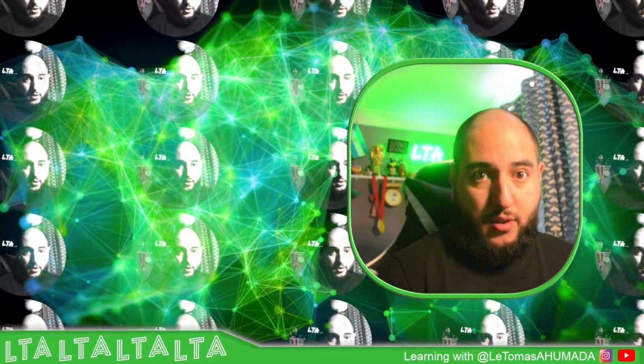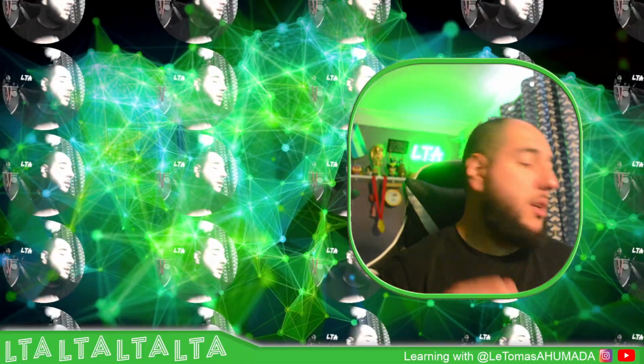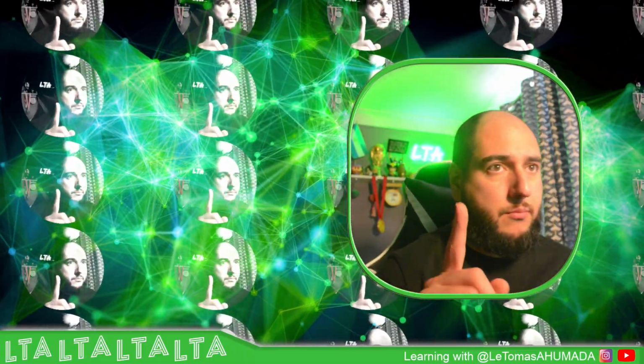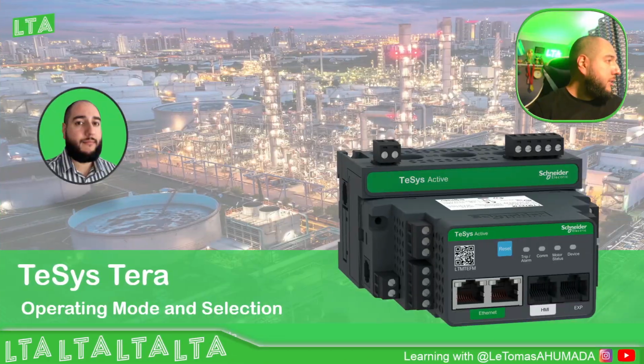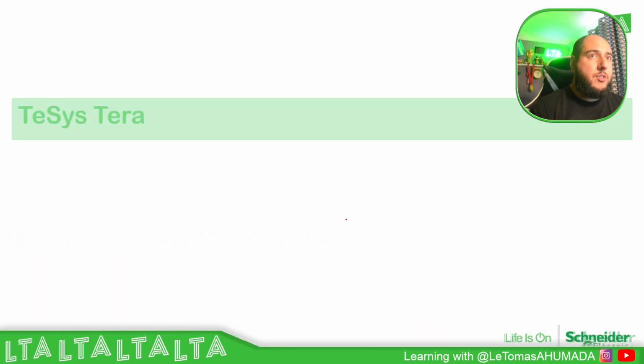In this video what we're going to see is the operating modes and selection that we have on the TeSys Tera. So let's go to the software, to the presentation. On the TeSys Tera we have different ways to indicate how we're going to make the start and stop, and we have different ways to select the source of how we're going to make the stop and run. That's what I'm going to focus on in this video.